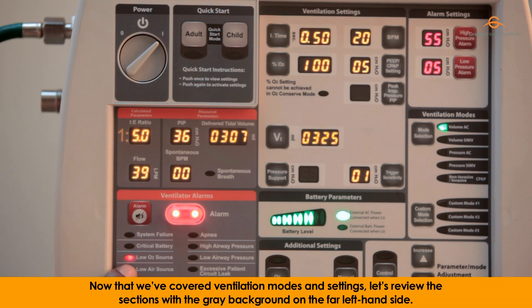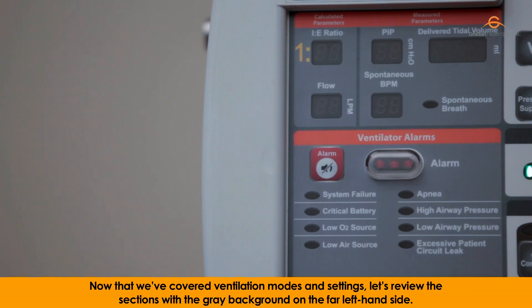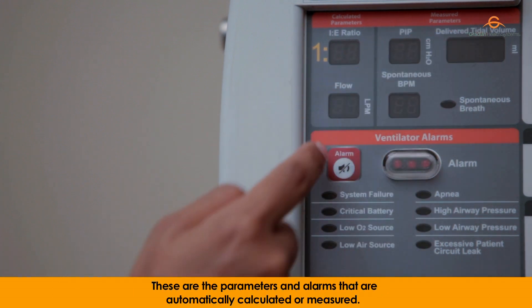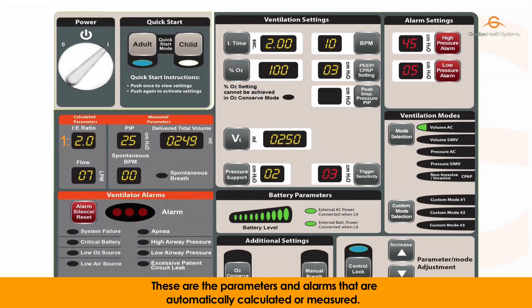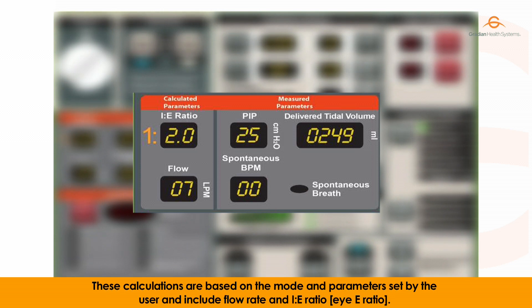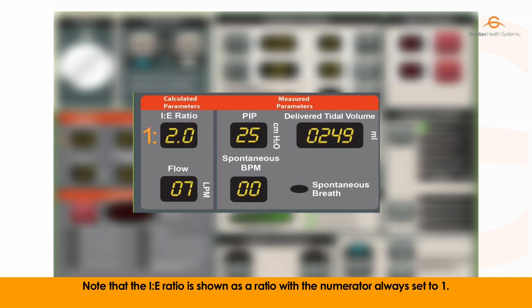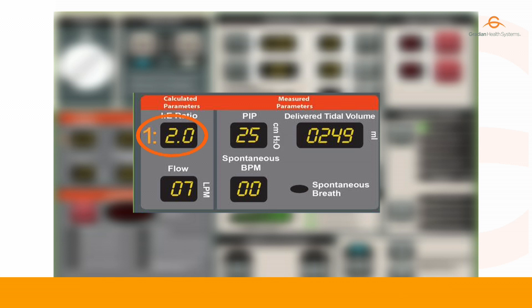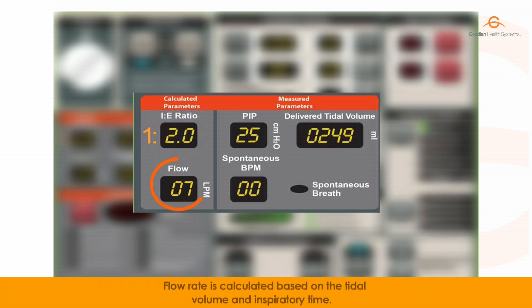Now that we've covered ventilation modes and settings, let's review the sections with the grey background on the far left-hand side. These are the parameters and alarms that are automatically calculated or measured. The first is the calculated parameters panel, which includes flow rate and IE ratio. The IE ratio is shown with the numerator always set to 1, calculated based on inspiratory time and breaths per minute. Flow rate is calculated based on the tidal volume and inspiratory time.